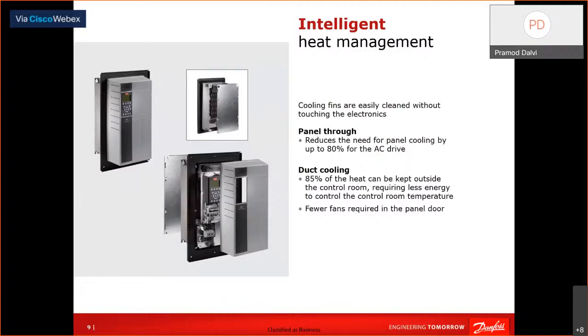We have cooling fans which can be easily cleaned, because normally the fans get dust or moisture. This is one point where we stand out from the competition. We have panel through mounting, where the heatsink can be mounted outside, so there also you can reduce the losses. And then we have duct cooling. This is a unique feature of Danfoss where 85% of the heat can be taken outside the control room, and the balance 15% only is your HVAC need.